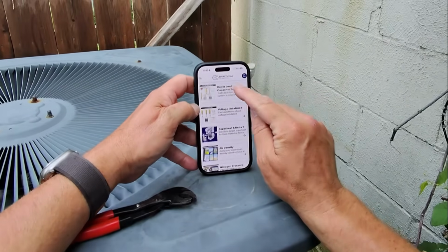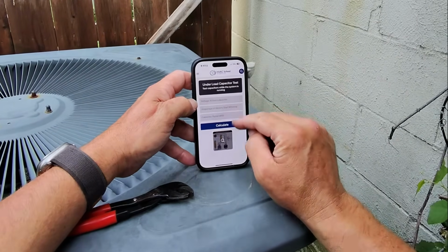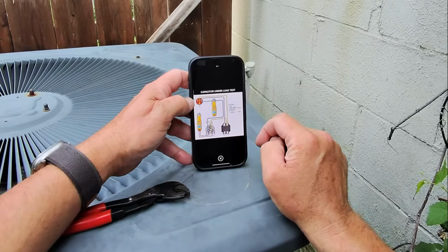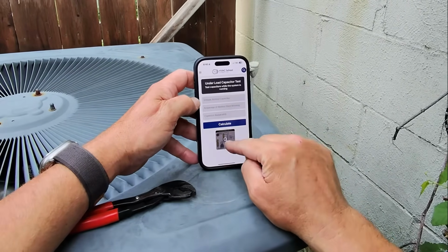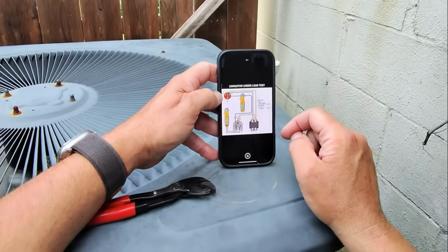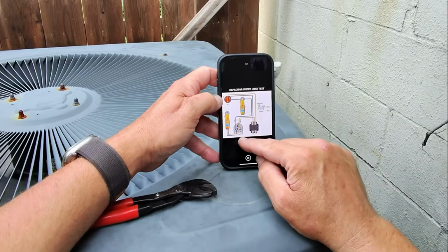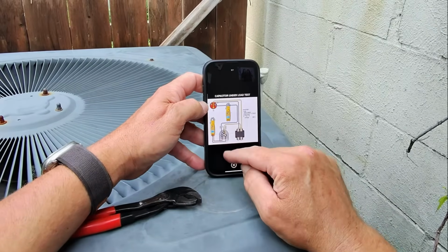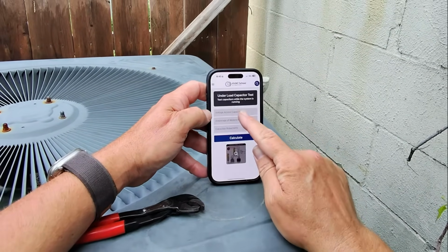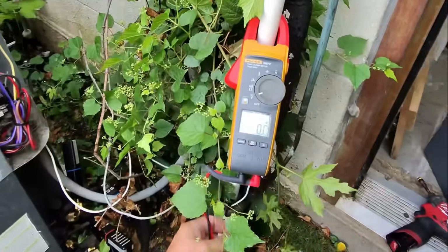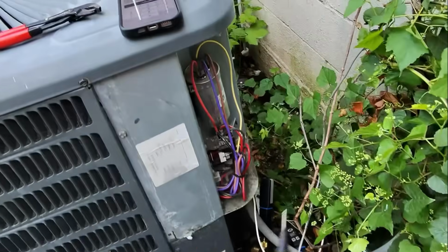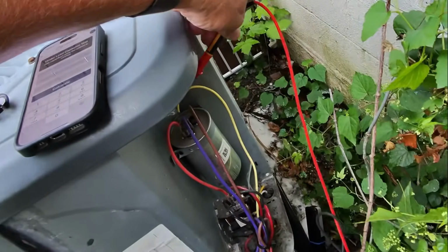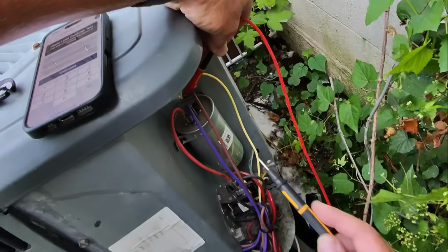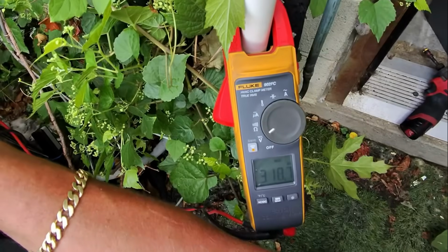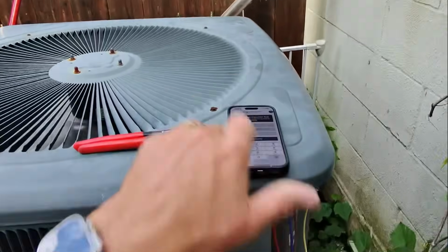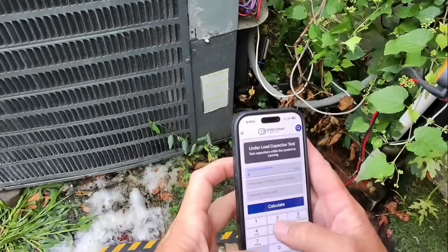We're going to go to the under-load capacitor test. And first thing we're going to do is look at the picture if you don't know what you're doing. We're going to take a measurement of the voltage across the contactor. Sorry, of the voltage across the capacitor. So we're going to take one lead to our common, one lead to our HERM, and we're going to enter in that voltage right there. There's our voltmeter right there. All right, carefully, we're going to have one lead right there, one lead right there, and we have 320. Okay, let's put those numbers in, 320.